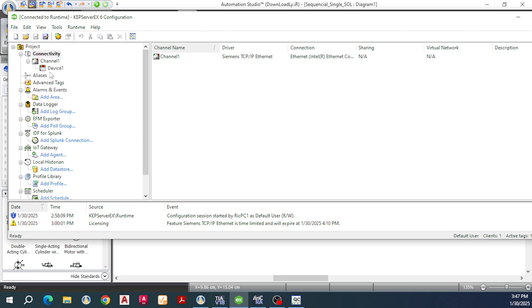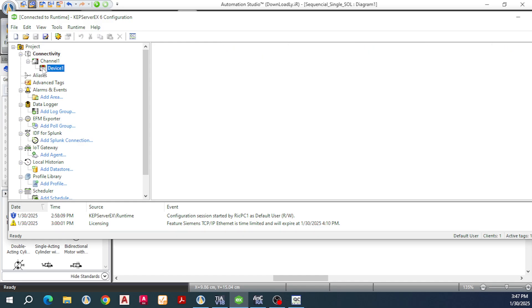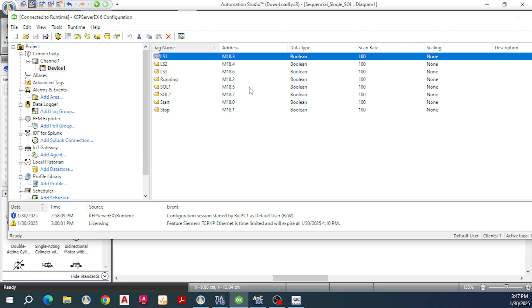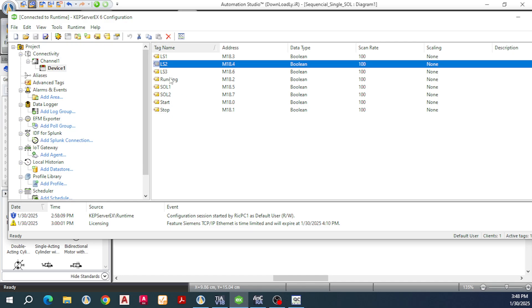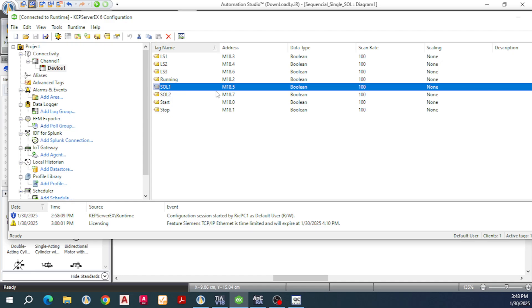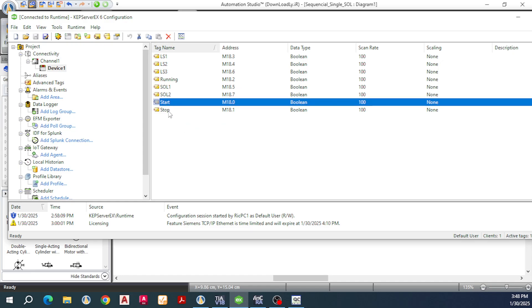After you create channel one, you need to create a device. I will create device one. In that device one, you can create tags for specific components. For example, the name tag is limit switch number one and the address I use for the Siemens PLC is the M memory address. Then limit switch number two, limit switch number three — these are for starting and stopping the system — solenoid number one, solenoid number two, start, and stop.